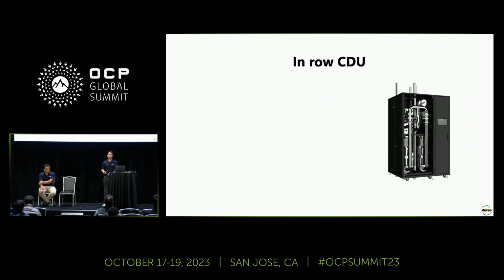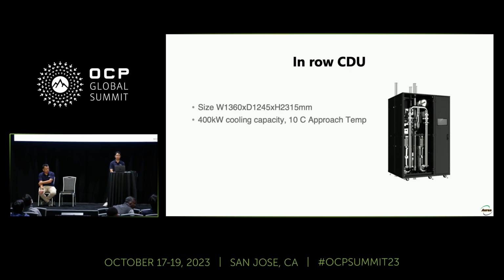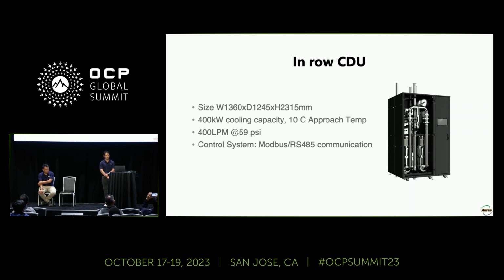So you guys might notice at the very end of the video, we got a gigantic piece of equipment. It's our in-row CDU, and the size is about 2 racks wide. It can support up to 400 kilowatts cooling capacity with the 10 degrees Celsius approach temperature. So it's very suitable for multiple rack cooling. It can support up to 400 LPM at 59 psi. The control system is a little different from the HRU. It's Modbus and RS485 communication.